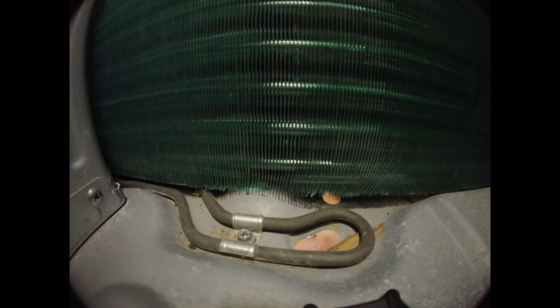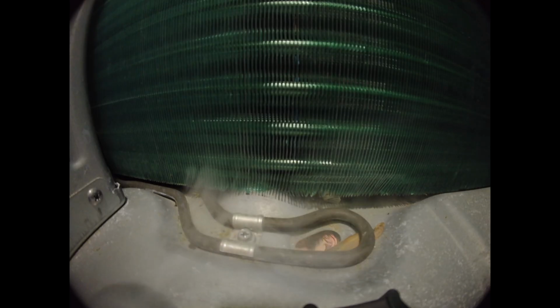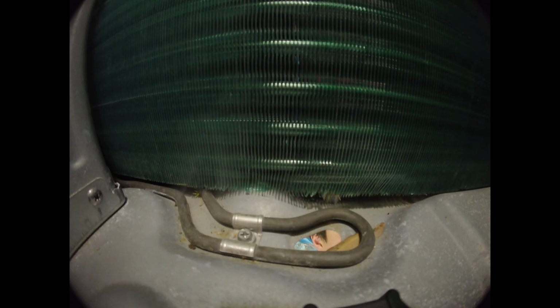Now, what we're looking at is the base pan of the Samsung. We're looking at the back part of the heat exchanger, and looking to the right of your screen, you will see some smoke that flows underneath the heat exchangers right there. Now this highlights the bypass sites flowing underneath the coil. Now looking to the left of your screen, we're going to show that it also happens towards the left of the screen as well, which further shows that the Samsung unit has a lot of bypass underneath the coil.